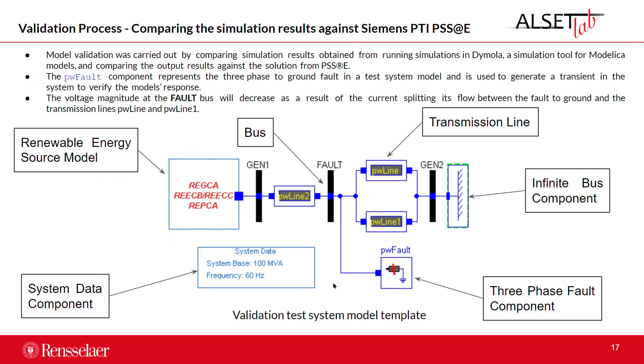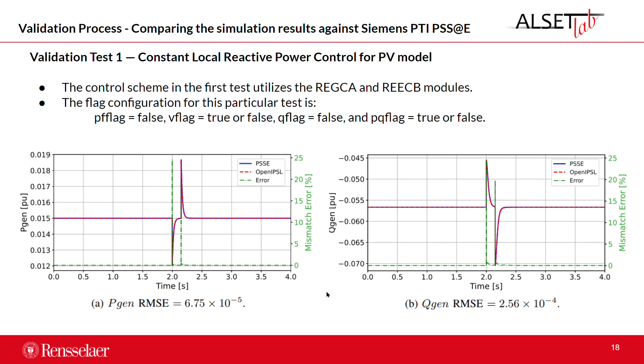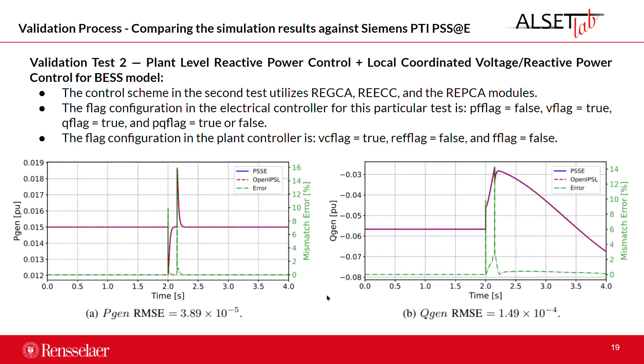The validation process was done through a test case system model template, where we apply a fault to the system and measure on both PSS/E and Dymola the resulting active and reactive power injected by the renewable energy source. The active and reactive power for test one — a PV model with constant local reactive power control — had similar results, with a spike in the mismatch area only at the moment of the fault and the clearing moment. This is due to the difference in solver tolerance between Dymola and PSS/E. Test two, for the battery energy storage system with local voltage and reactive power control, also had the same agreement.